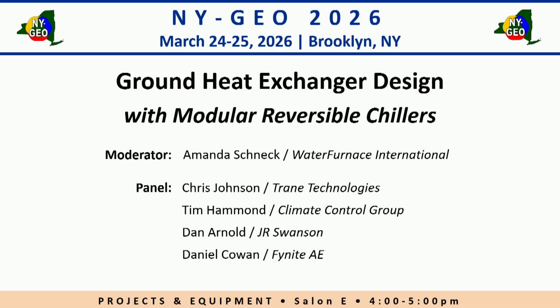So it all starts from looking at your load at the building level, and that feeds into the proper sizing of your bore fields, whether or not you can reduce it by 2 or 3 bore fields because you have simultaneous heating and cooling. But if you're just looking at peak loads, you're never going to find that out. You're never going to get the right sizing of the bore fields.